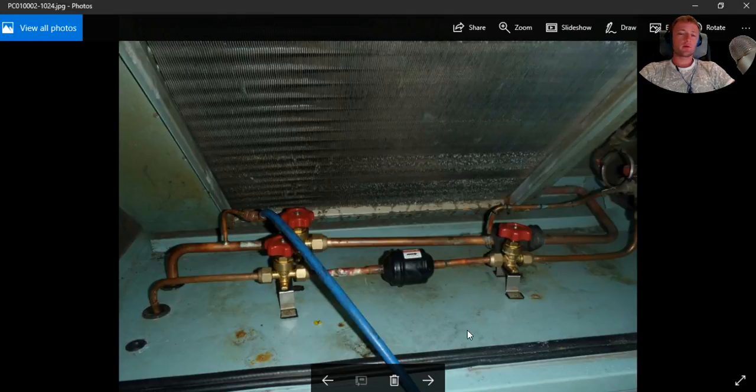Next, very important, some manufacturers or shipbuilders set slightly bigger air conditioners, so they can handle, everything must be calculated, about 15 or 20% more capacity than it requires. If somebody calculates, let's say, that it needs 10,000 BTUs to cool down a space of 20 square meters, let's put a little bigger. You will have some energy losses, but the thing I'd like to tell is that your system will be more effective. So just keep this in your mind.